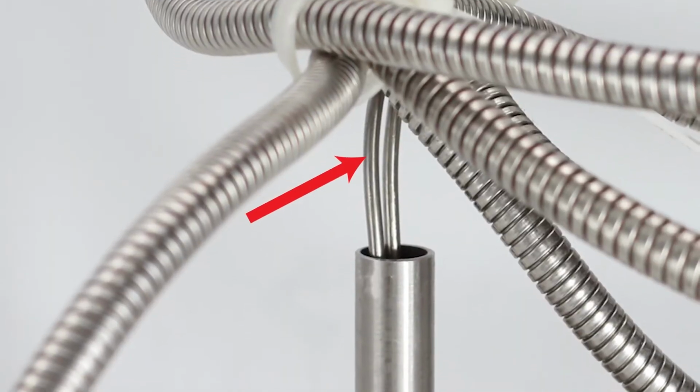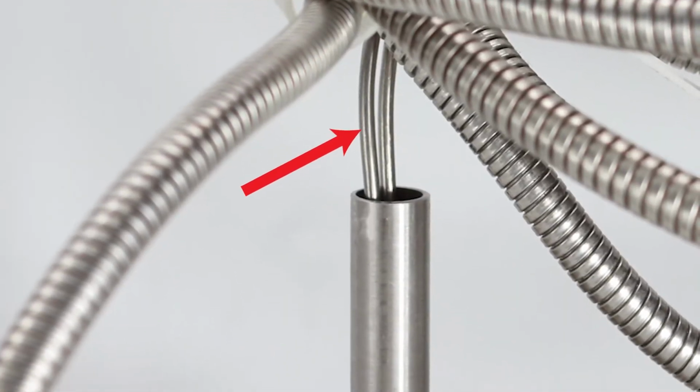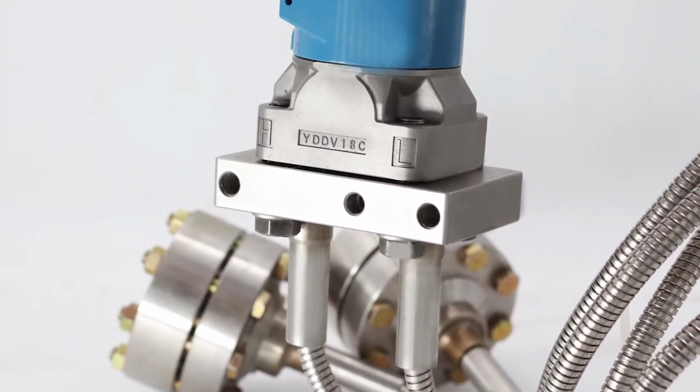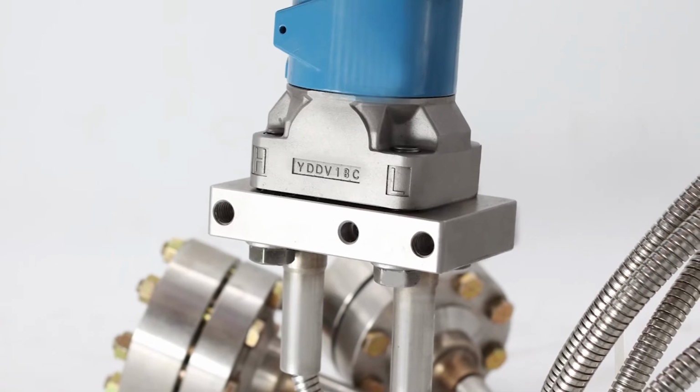Our patented temperature compensated remote seal system uses a separate tube that runs in conjunction within the same armor with the traditional capillary tubes that you generally see. The compensating tube that runs in conjunction in that armor dead ends at the remote seal, but it's connected to the opposing side.